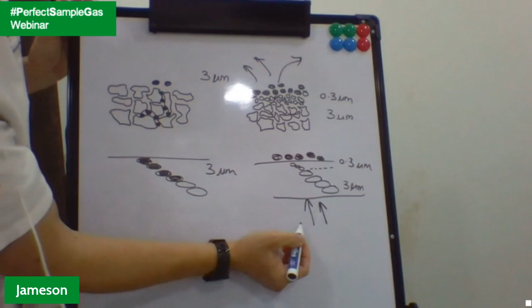So if I draw this way, if you look at the filter layers, the upper layer is 0.3, the lower layer is 3 micron. The particles here are bigger than 3 micron, but stay on top. They have no chance to go in. And when I have a back purge, the air will go through all the way, and then they just get purged out, flushed out. This is called a back purge.